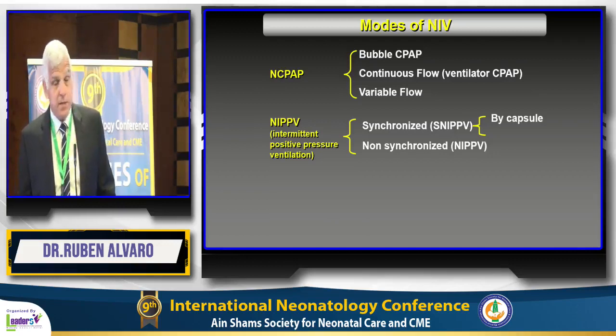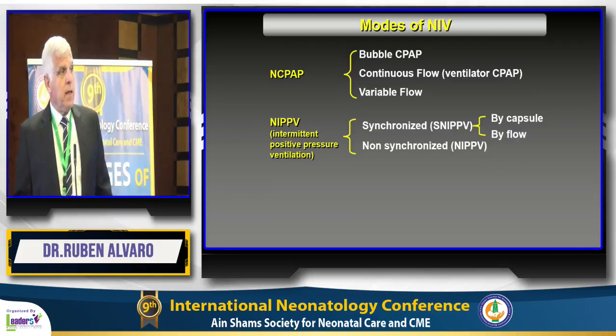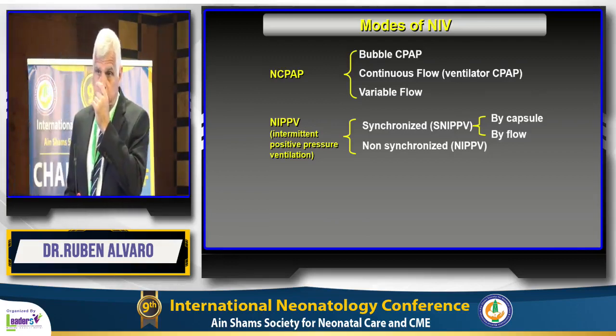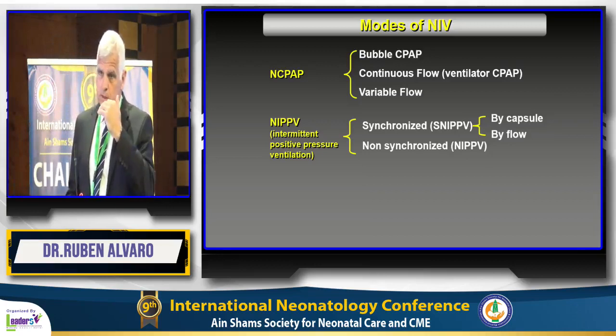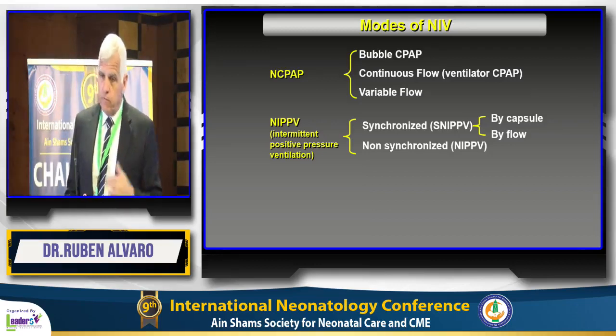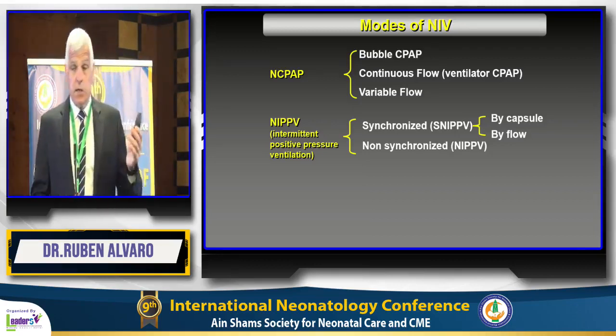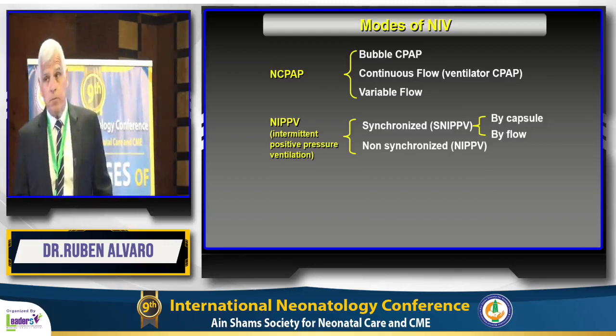The other form is a newer one, by flow. You basically have a flow transducer at the nose that picks up negative pressure triggered by the baby's spontaneous breathing, and that will hopefully deliver that breath. These are newer machines - there are not many studies yet to see if the synchronization obtained by flow is better than by capsule, or if it's sensitive enough.